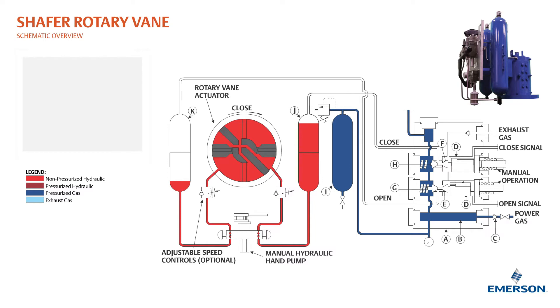Power gas connected to the poppet block flows past the power storage tank check valve, through the power gas strainer, and fills the optional power storage tank. Power gas also flows into the backside of the poppet block, forcing the power poppets onto their seats.